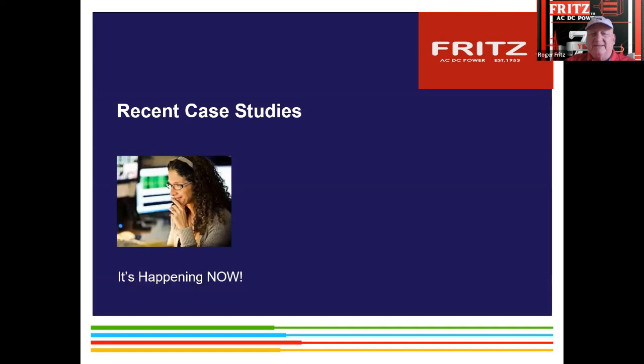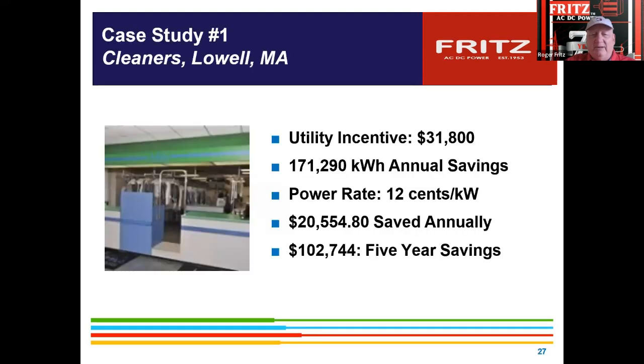These are just some of the case studies that we were involved in over time. This happened to be a cleaning facility, a dry cleaning outfit up near Lowell, Massachusetts, that we installed. From the utility company, there was $31,000 worth of incentive available that we got. We were able to get 171,000 kilowatt-hours in annual savings. 12 cents a kilowatt-hour ended up being the rate, and this is the actual kilowatt-hour amount, not the demand. There was some demand reduction, but we were talking specifically about kilowatt-hours saved. And this ended up being about 102,000 in five-year savings. And I think that was about 30 or 40 drives installed there.